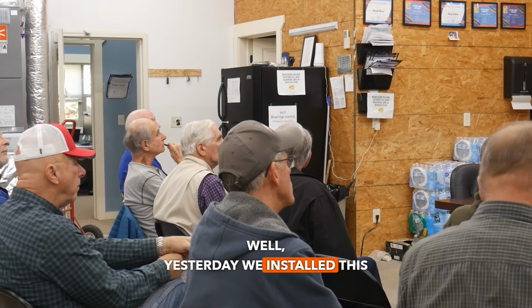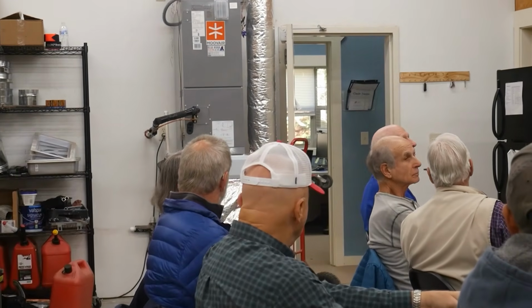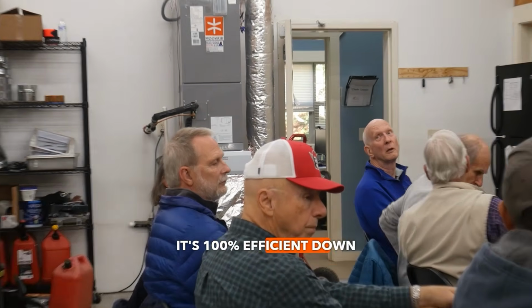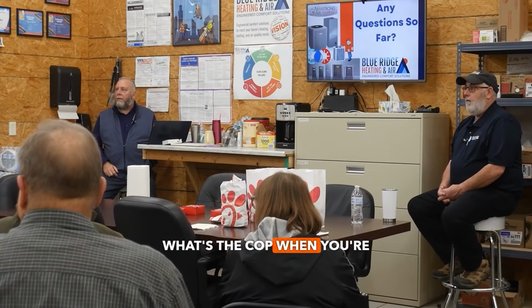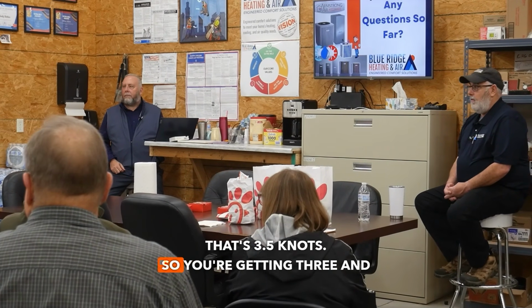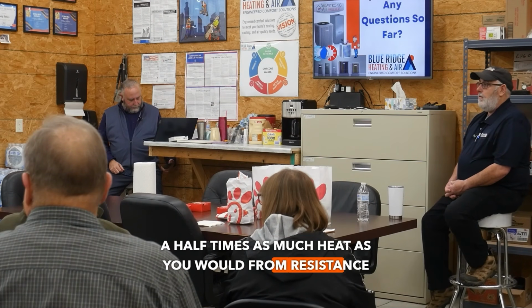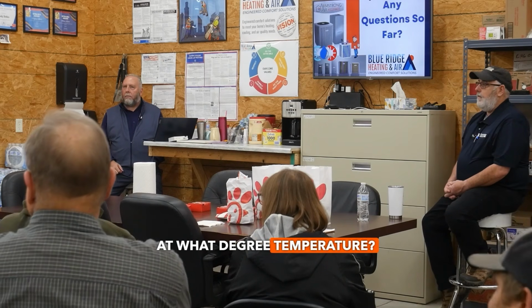Well, yesterday we installed this equipment, the Move Air. It's supposed to be 5 degrees, is that correct? It'll go down to, it's 100% efficient down to -4. The COP on that is rated at like 3.59, but that's under optimum conditions. What's the COP when you're down 5 degrees? That's it. That is it. That's 3.59. So you're getting 3.5 times as much heat as you would from resistance heat. That is correct. At what degree temperature?